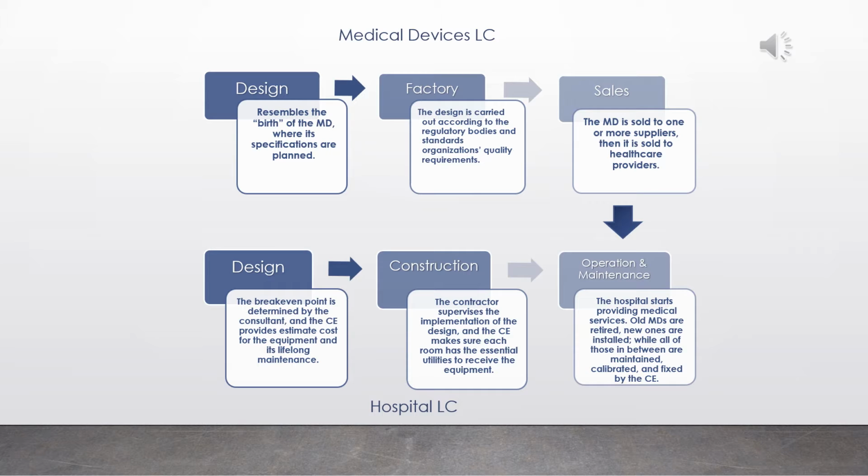The clinical engineer participates in the feasibility study, where he determines the break-even point, which is the point in time where the owner will recover their investment and start making a profit. In this phase, the clinical engineer also provides estimate and maintenance cost of medical equipment.